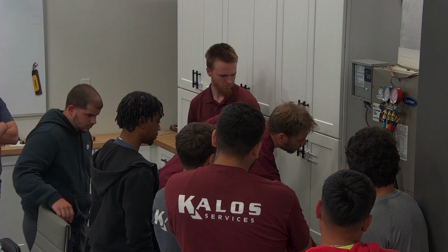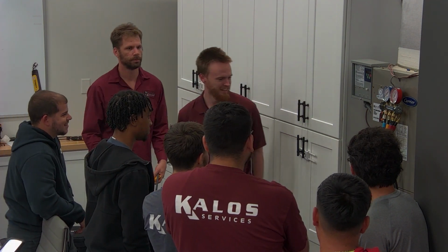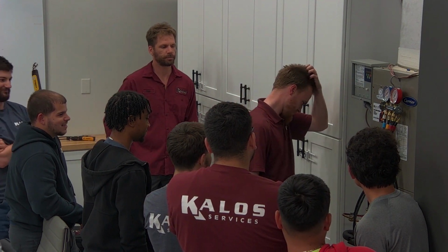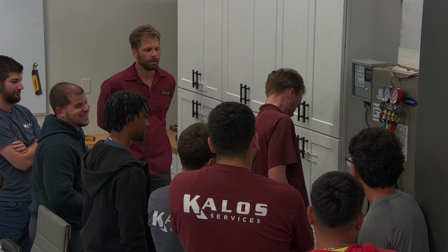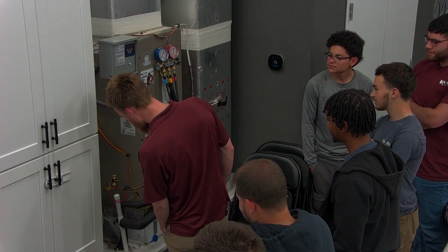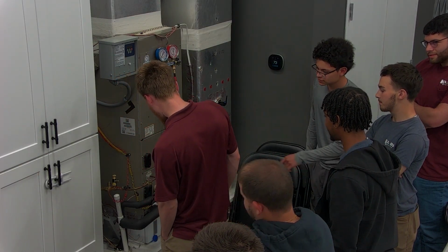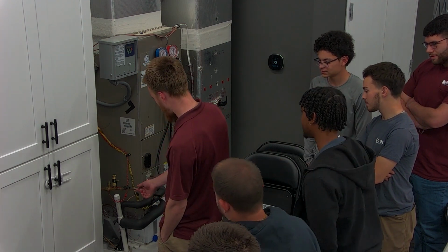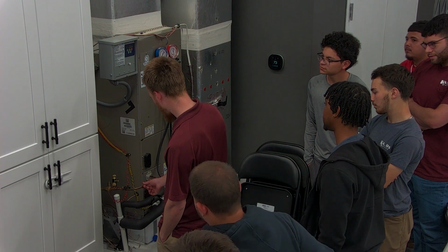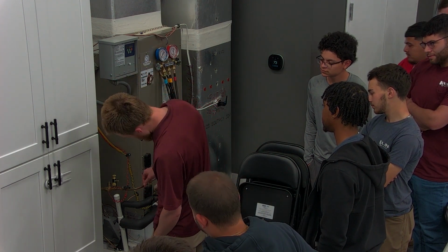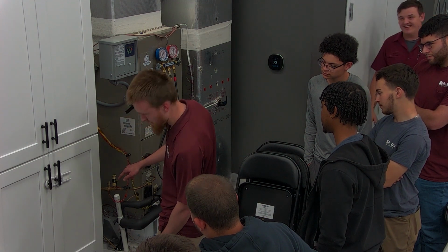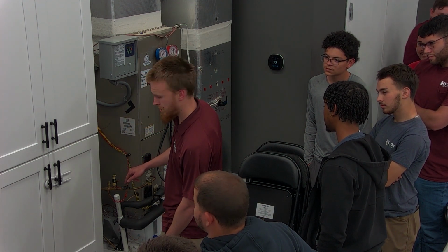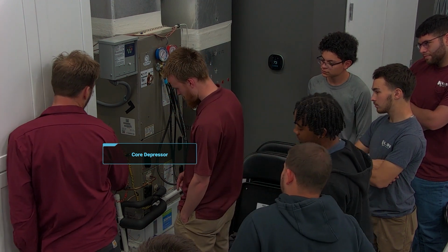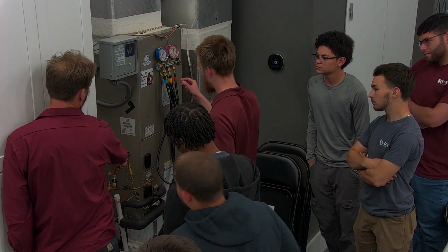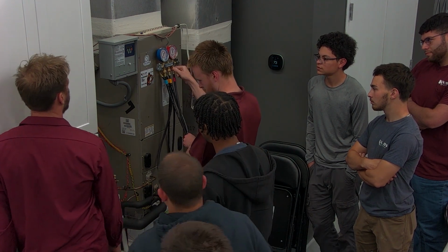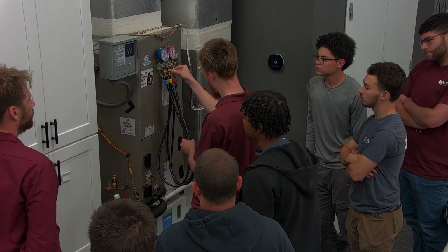Let's go, Alex. Pretend you're outside. What line is that? This one? The liquid line? Yeah, same as hooking up at the condenser then, right? Pressures are the same all the way through. Did you say the Schrader's in? Oh, this is a quarter-turn fitting, so it's not spraying right now because I haven't tightened this down. So this is the same as a low-loss fitting.